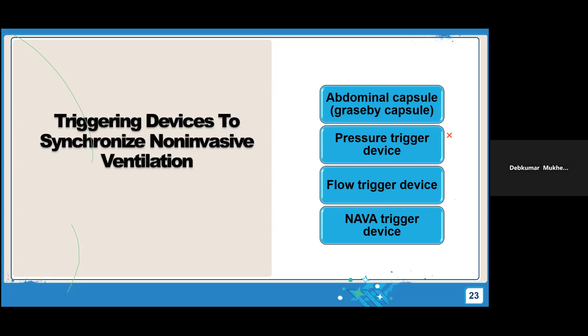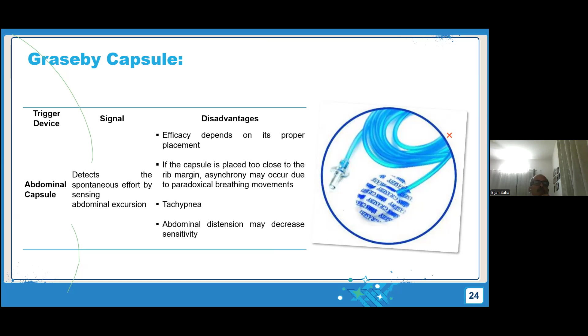So one is the abdominal capsule. What is the abdominal capsule? It is just like your respiratory probe. It's a balloon which is inflated and connected to a pressure transducer. Because of the abdominal movement, the ventilator will recognize that it is a breath. But the problem of this device is that it may show some artifact, because if there is a hiccup or some cough or some seizure, there will be a lot of artifact. This abdominal capsule was marketed by one ventilator, the Infant Star ventilator, which is no more marketed nowadays. So with the abdominal capsule, immediate triggering may be possible, but the problem is there will be too many artifacts. Next slide.